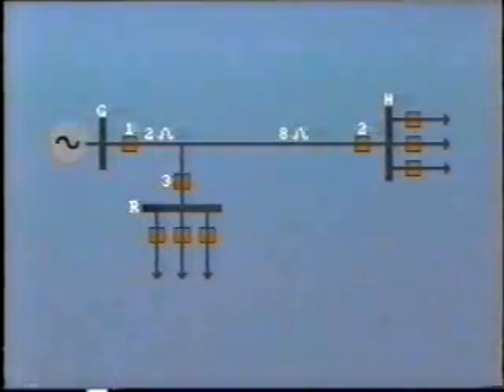Even the first zone can be difficult to set under certain circumstances. For example, the transmission line may feed more than one bus or terminal, as shown here. The tap to bus R is located fairly close to bus G. The impedance of this portion of the line, here, is only 2 ohms, while the remainder of the line is 8 ohms. The section of line to the bus R is quite short, having an impedance of only 1 ohm.